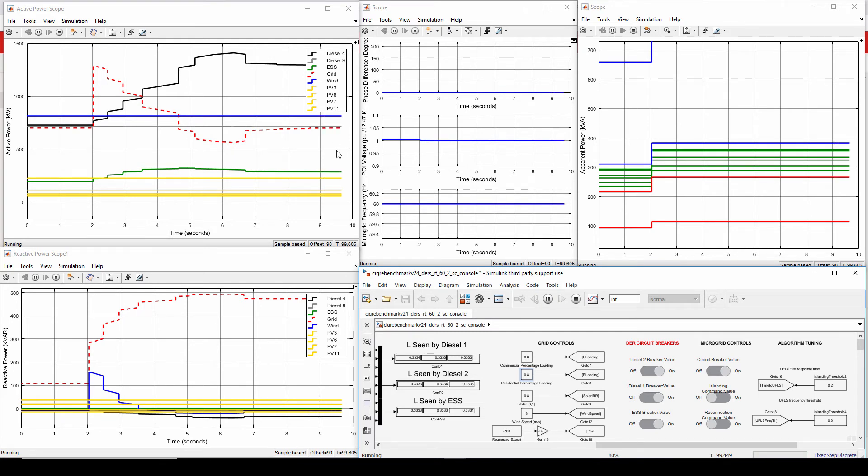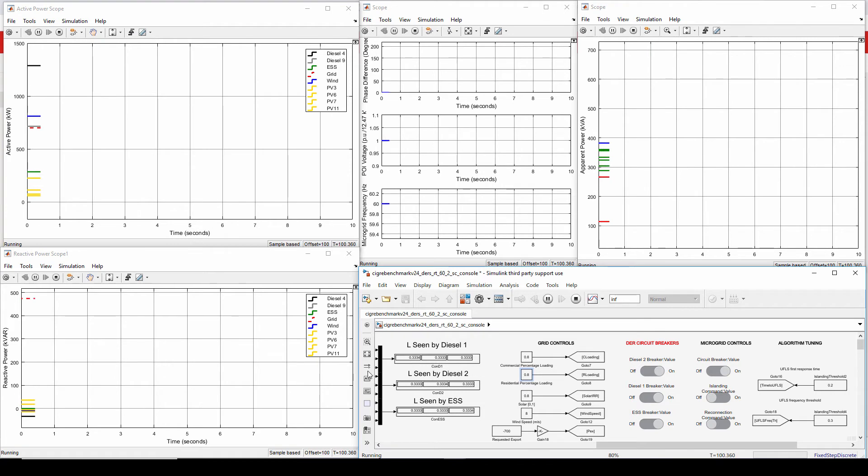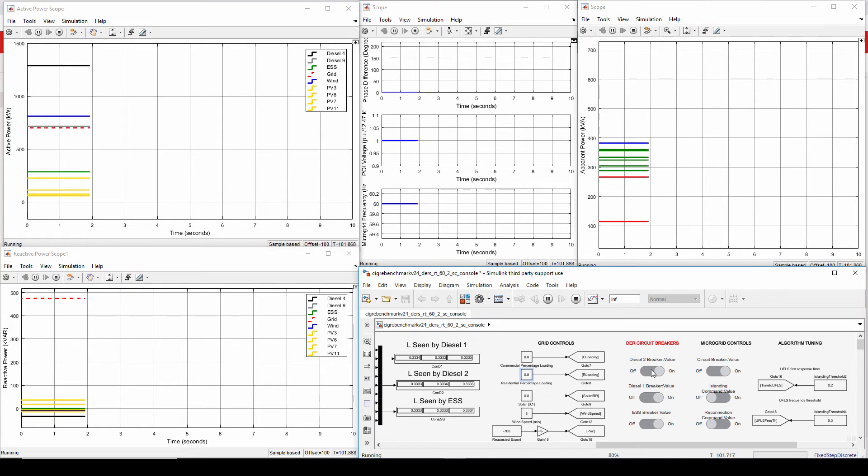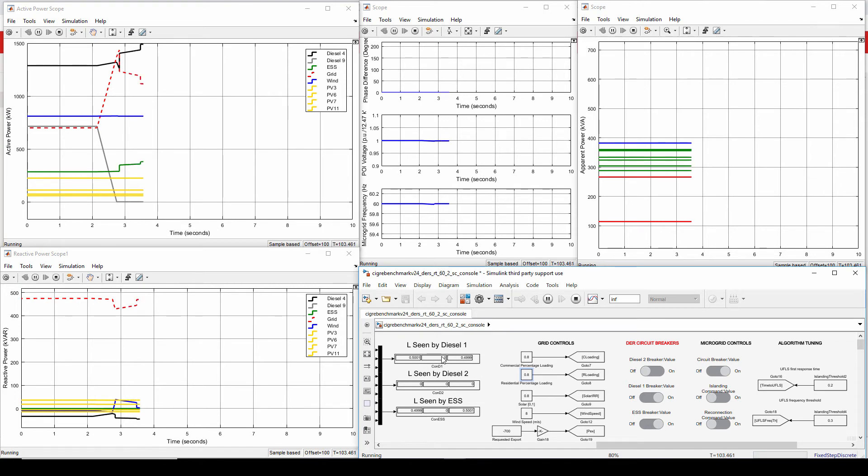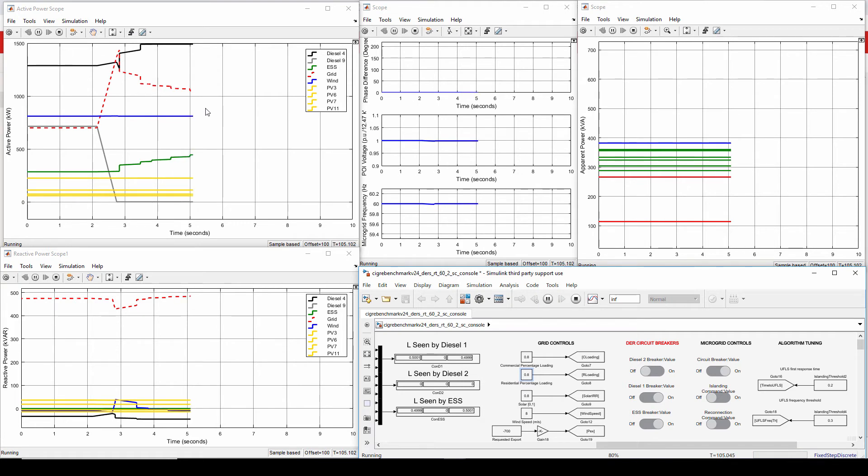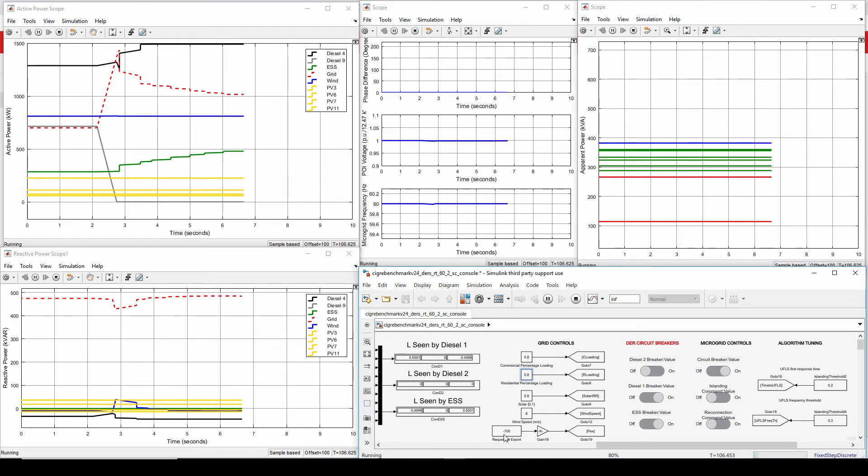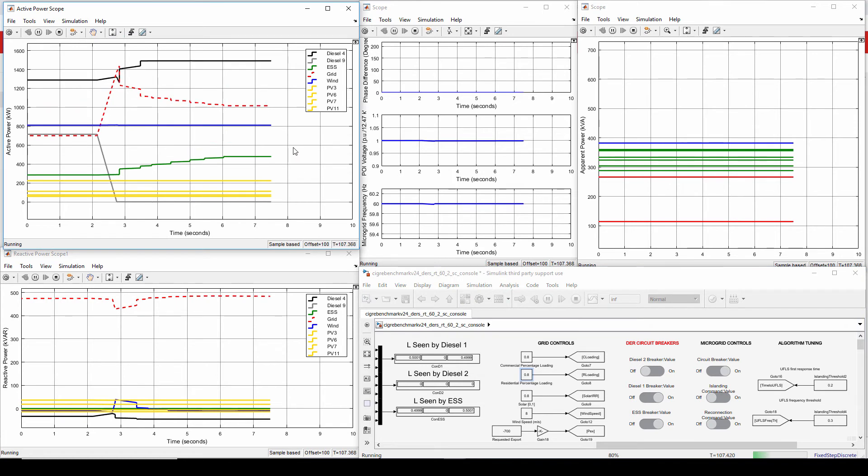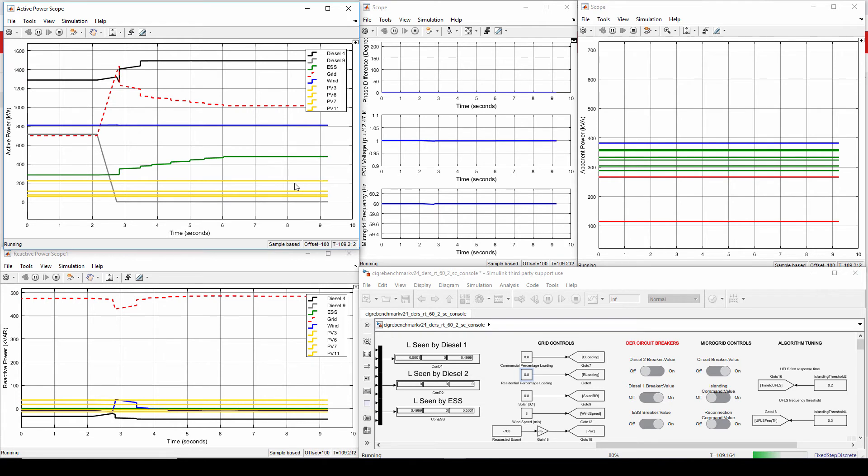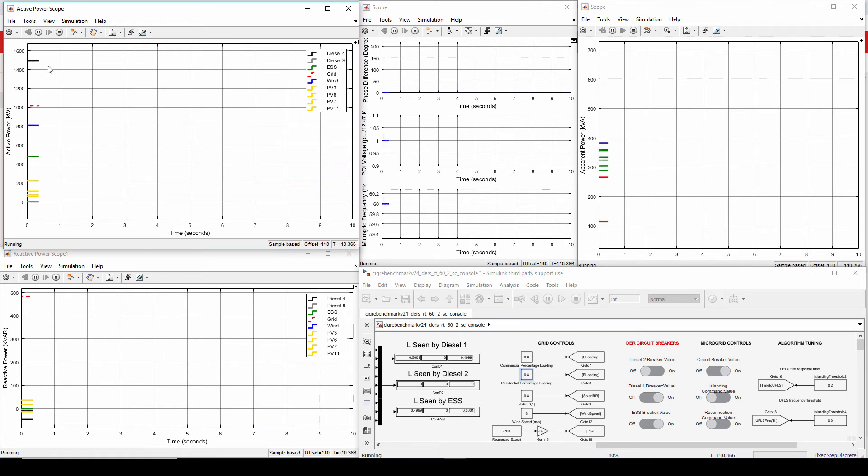Okay, so before I simulate islanding, I'm going to trip diesel 2 again and show you how it will play out and how the L matrices are going to update accordingly. So the diesel 2 is tripped. The distributed control system was able to update its connectivity matrix, but now actually there is not enough power by the ESS and the diesel 1 alone to fulfill the 700 kilowatts requirements. So it's going to be stuck there. So we will have to continue the simulation as is. Now the ESS and the diesel are already generating their maximum power output.